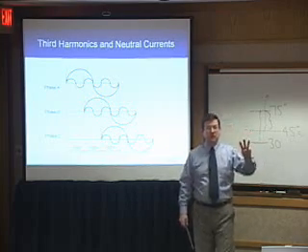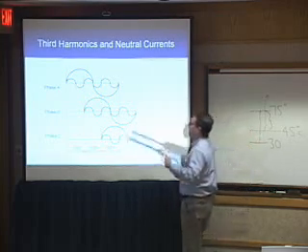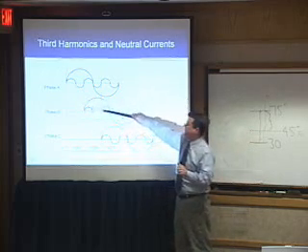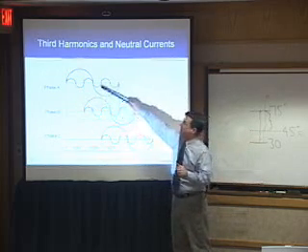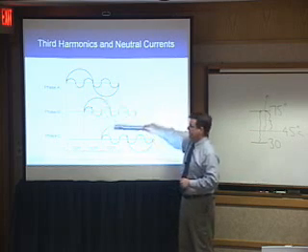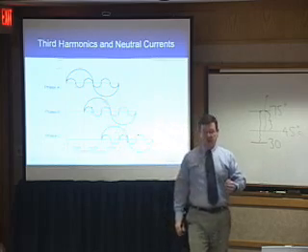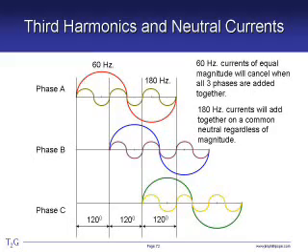The problem is third harmonics — they repeat every 120 degrees. The third harmonic of phase A is in phase with the third harmonic of phase B, and that's in phase with the third harmonic of phase C. So the third harmonics not only do they not cancel like the 60 Hz currents do, they add if they happen to be on a common neutral.